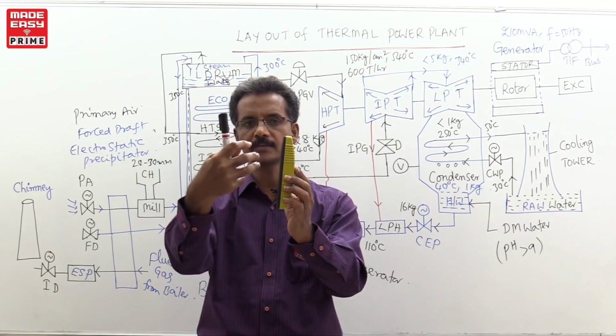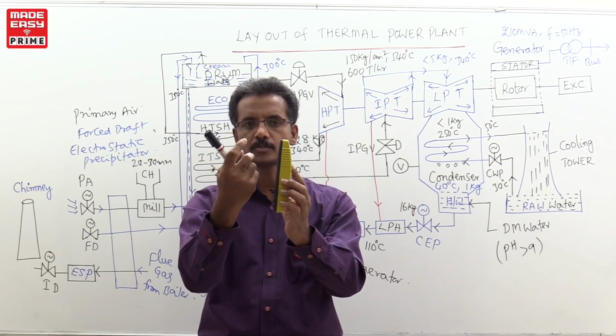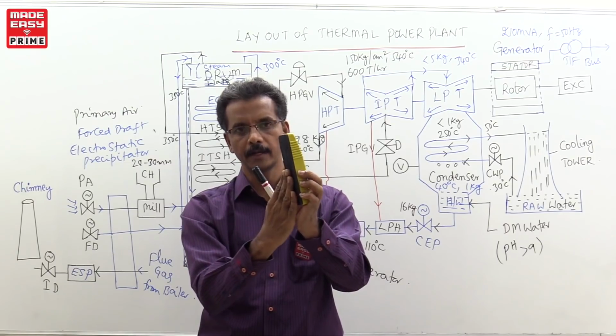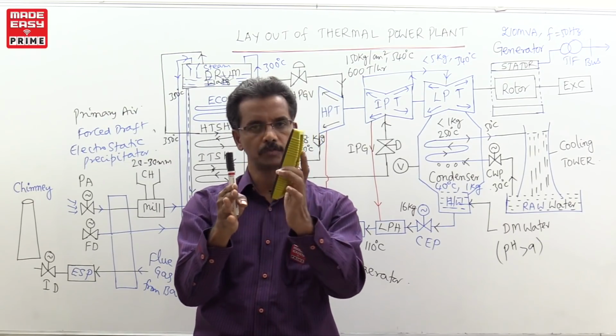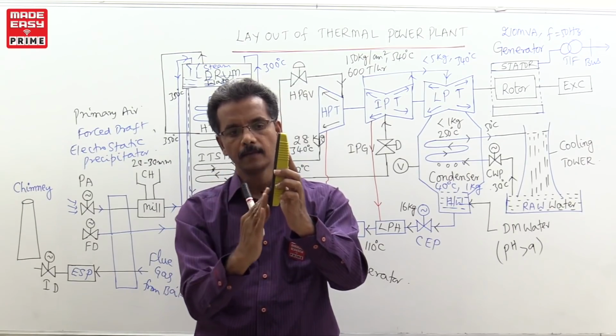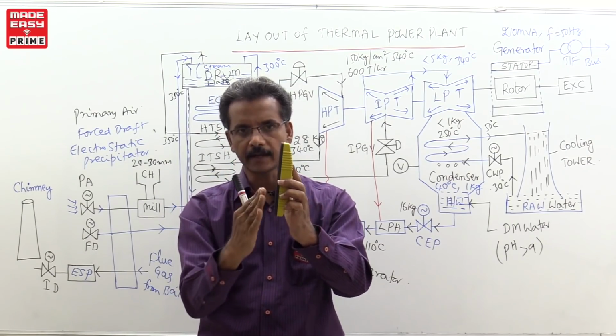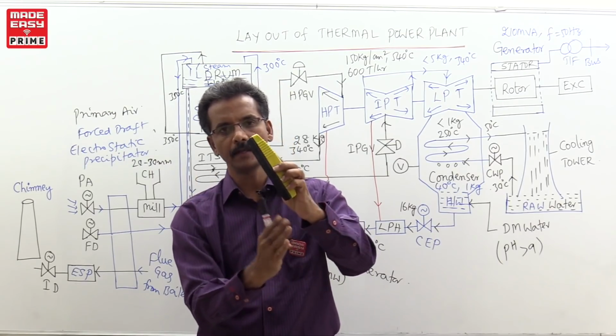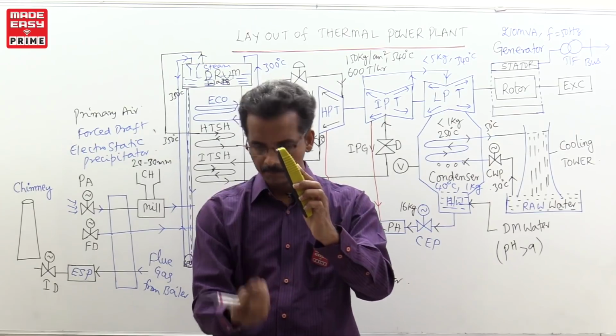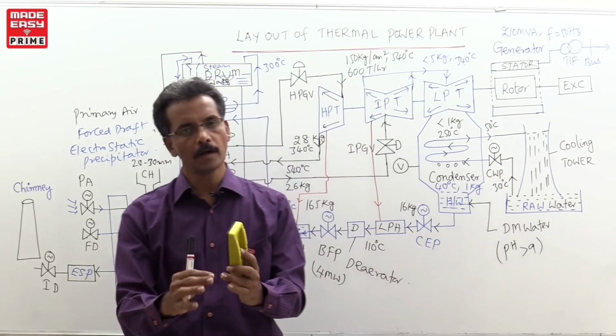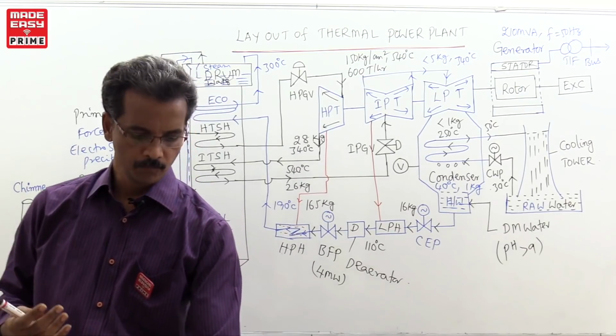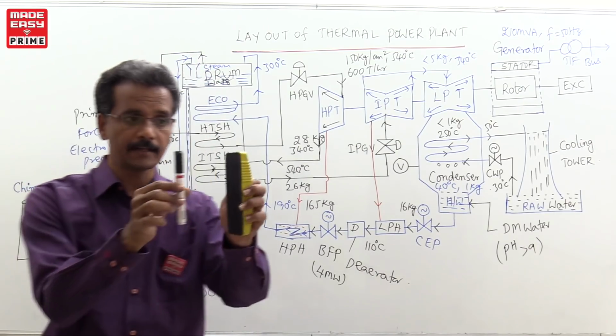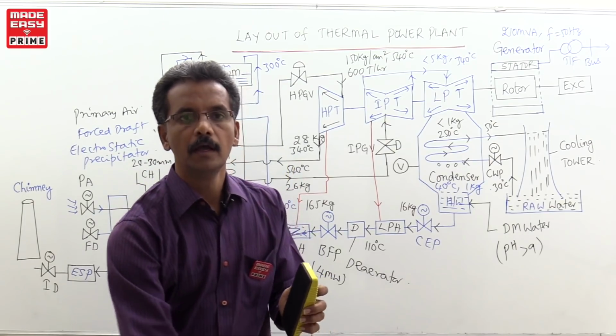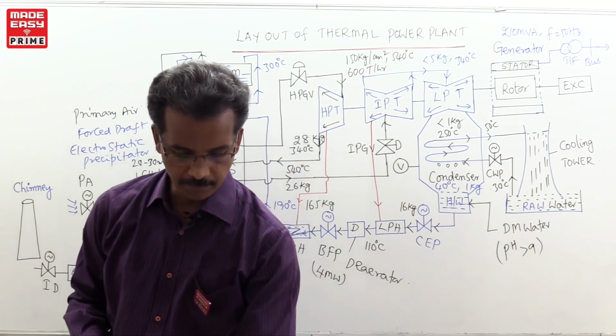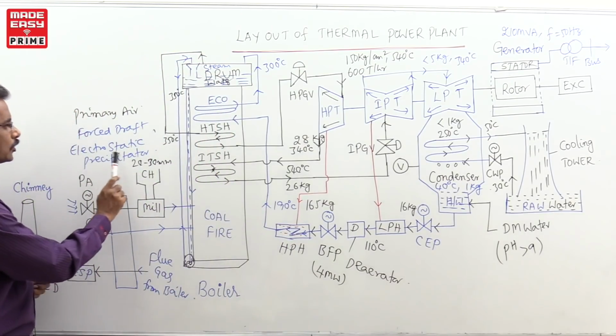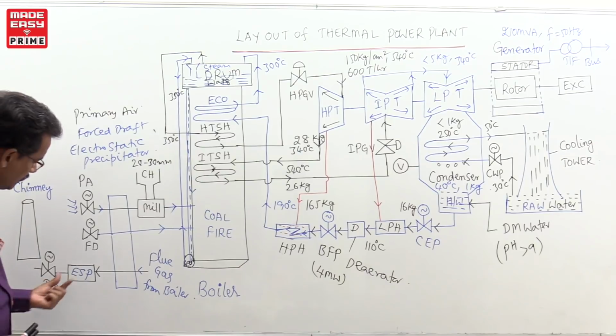Now what will happen? The ash has positive and negative particles. Positive particles of ash will be attracted toward the negative plate, and negative particles will be attracted toward the positive. The ash particles attracted to these plates are removed by hammering, and the ash is collected, mixed with water, and dumped into the ash pond. Right. This is the basic principle of using an electrical field for the collection of ash, which we use in the electrostatic precipitator. This is also one more important question. What is the functioning of ESP?